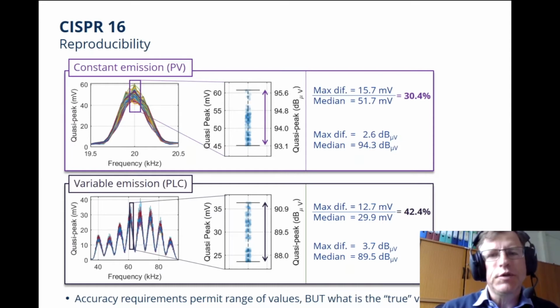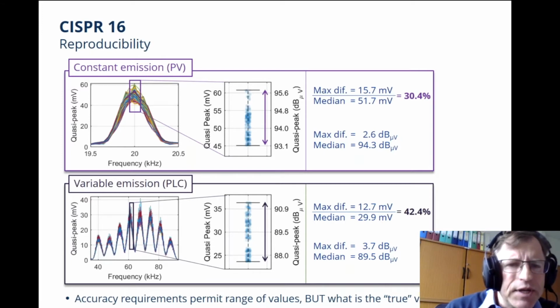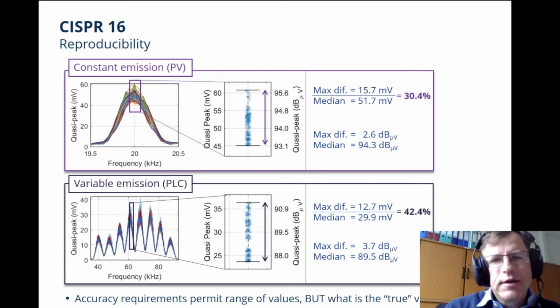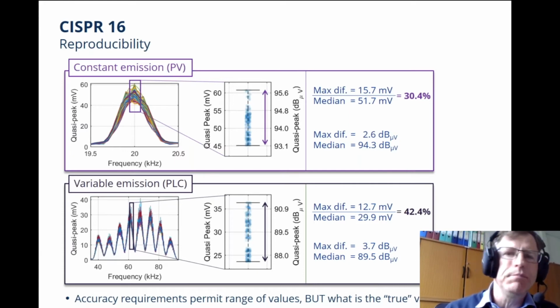So 30.4% for the PV emission in the peak, and 42% for the variable PLC emission at, I think, 54 kilohertz, or no, it's 60-something kilohertz. From that point of view, that is well within the plus or minus 2 dB uncertainty, but the question is really, what is now the true value? Especially if you are close to the compatibility level, that would probably matter, because it will determine who is responsible to mitigate.